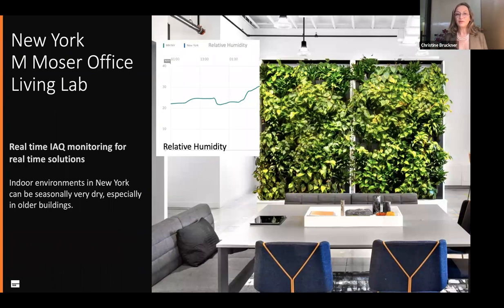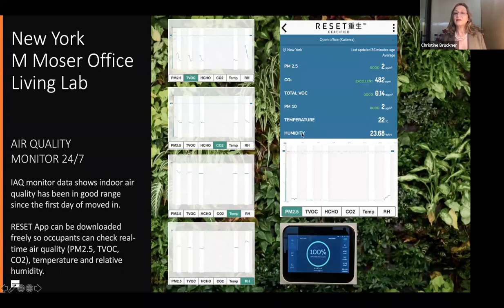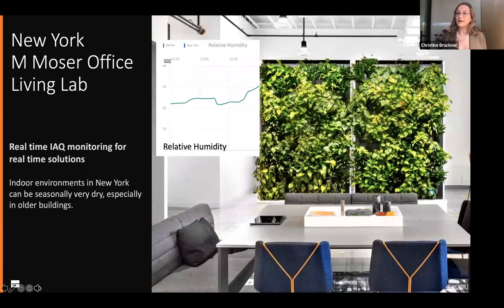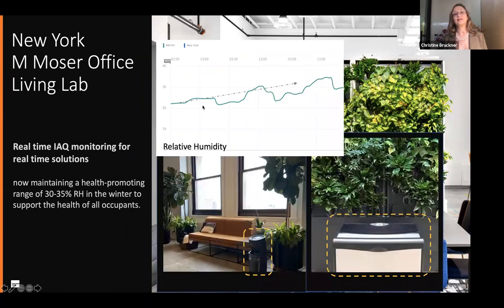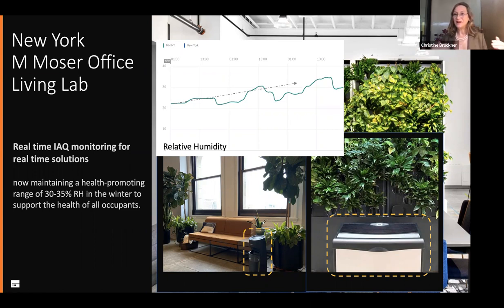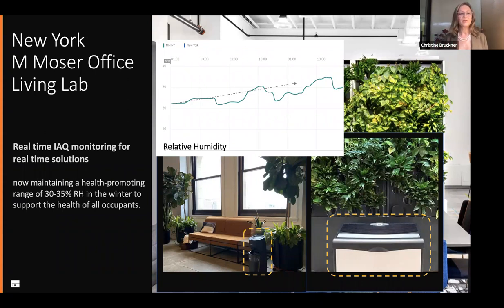For example, we found in the summary that humidity was at about 23–24% relative humidity — a little dry. As mentioned earlier, when humidity is dry we can be more prone to illness. So we immediately took action. Here you can see the relative humidity down in the 20s; we got some humidifiers — a very simple solution — and brought that to a health-promoting range above 30–35%. In the summer we have much higher rates. This is something you need to watch seasonally, daily, and just be aware of what's happening with your air quality.